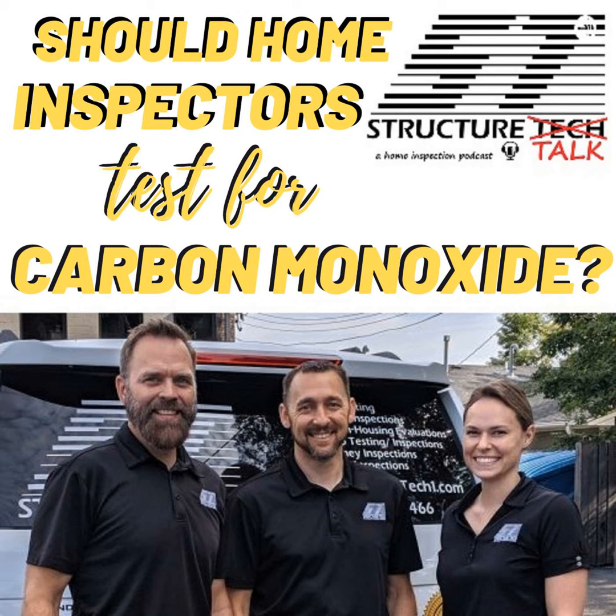I do. Yeah. And then that takes us to the sealed combustion high efficiency furnaces. Typically, you can identify those because you've got PVC pipes coming off, one for an intake, one for an exhaust, although sometimes you might just have an exhaust pipe coming off with no intake. And on those, what we do at Structure Tech typically is we will test the exhaust gas from the exterior where that exhaust pipe terminates on the outside of the house. Now, if it goes up through the roof, that's another story. If it's not accessible, you don't do that, but we'll try and test it from the outside.